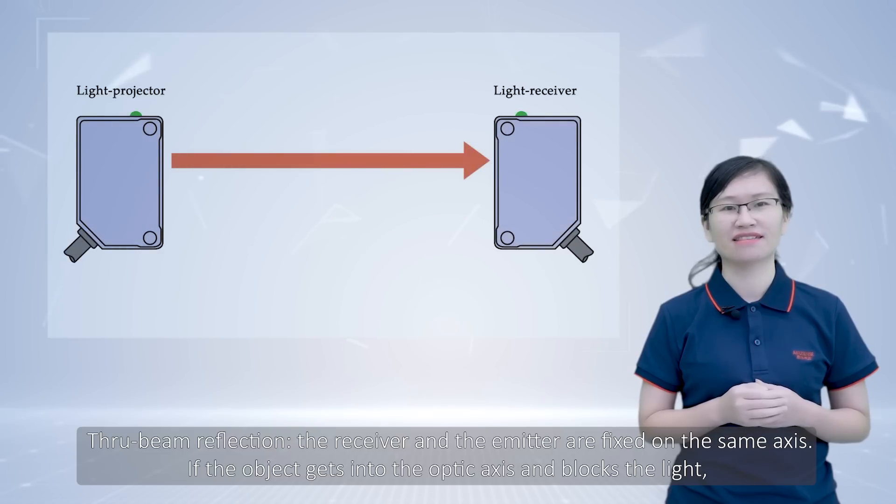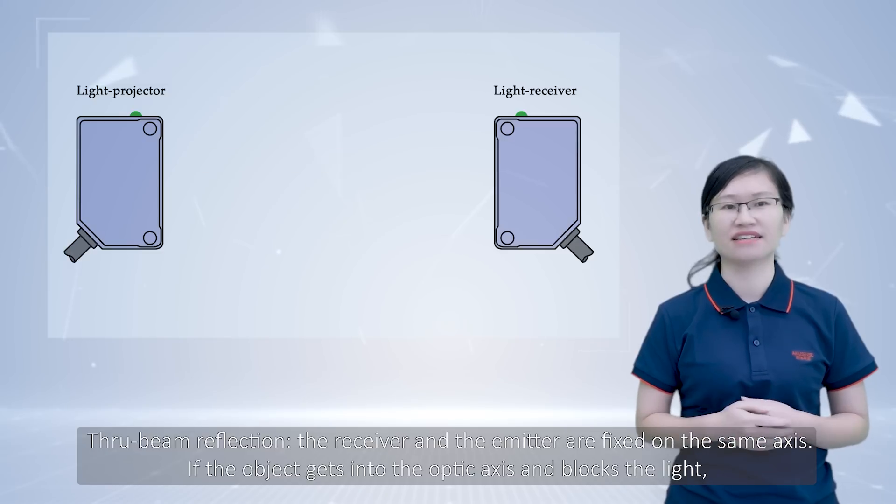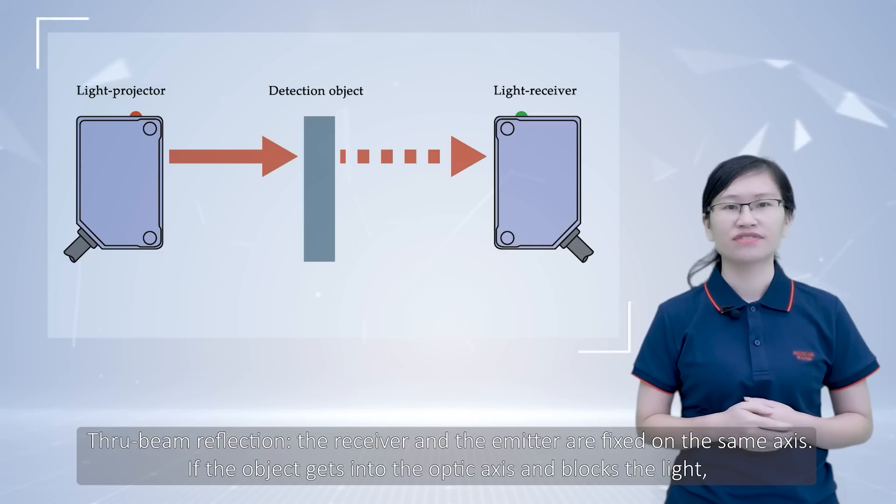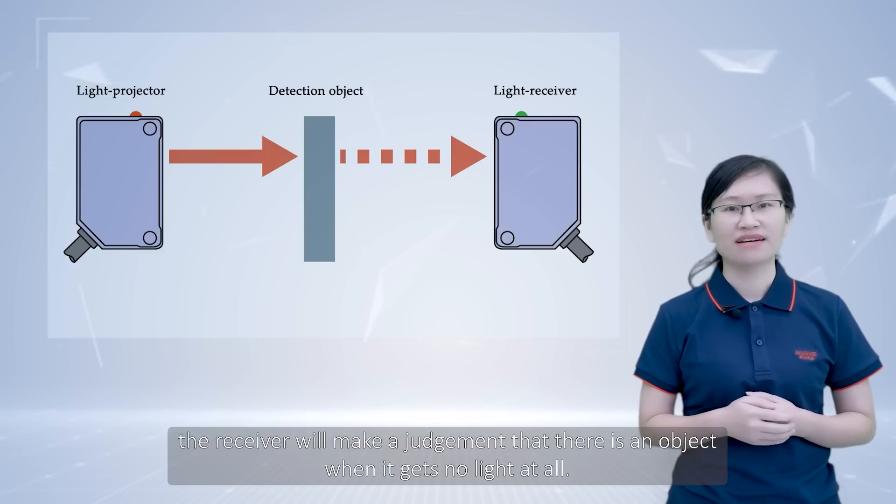For through-beam reflection, the receiver and emitter are fixed on the same axis. If the object gets into the optic axis and blocks the light, the receiver will make a judgement that there is an object when it gets low light or no light at all.